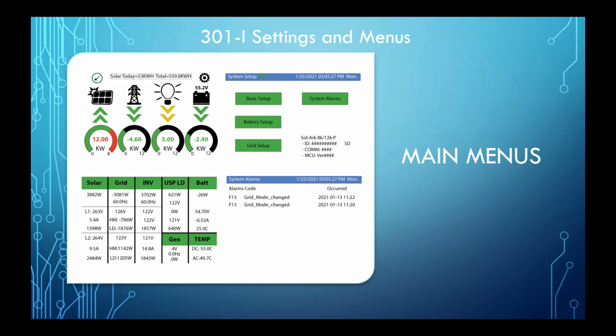One thing I did want to point out is if you are using our limited power to home feature, which does utilize the included CTs mentioned earlier, this is a screen that we would recommend using to kind of verify that the CTs are facing the right direction, they're on the right phase, and everything like that, and specifically under the grid column. So if you are calling in, this is a screen that we use quite often. It does give us a lot of great information. So it's a great screen to work from as well.